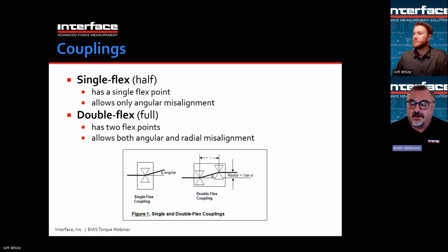So if you have 1 degree displacement and a double flex coupling, you can get a certain amount of radial deflection. The longer that coupling is, the farther the distance between the two flex points, the more radial. And there are actually certain couplings that have big tubes in the middle between the flex points to allow for extended amounts of radial misalignment.